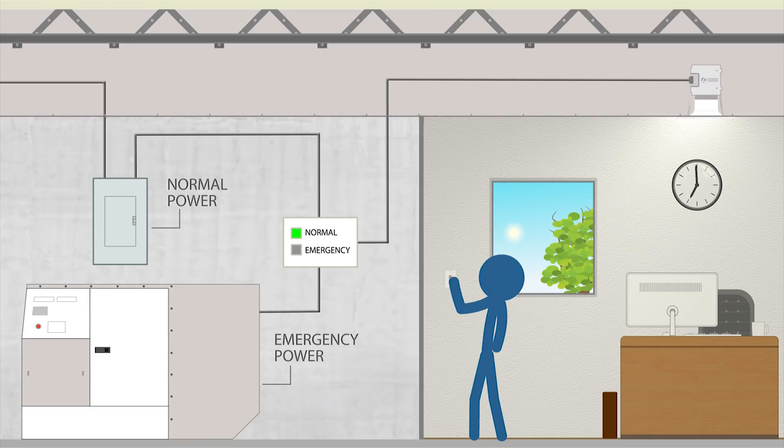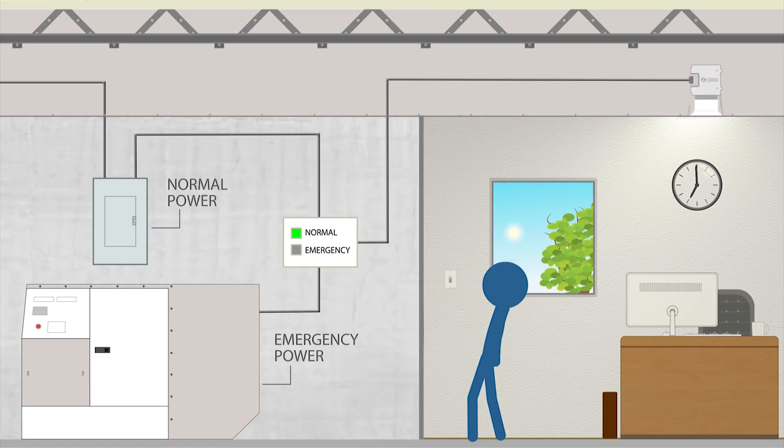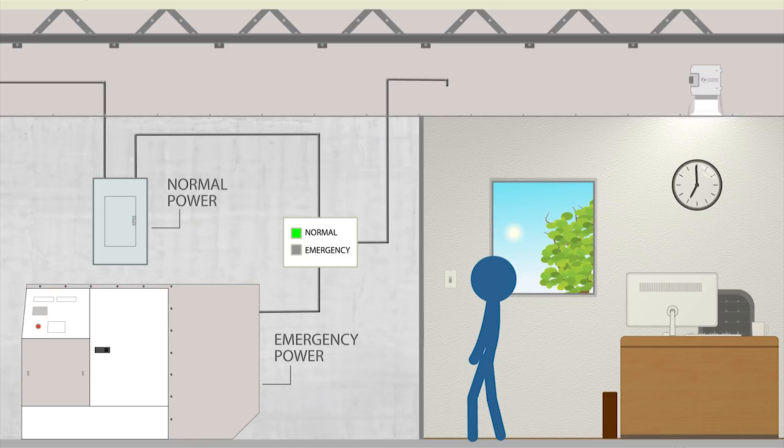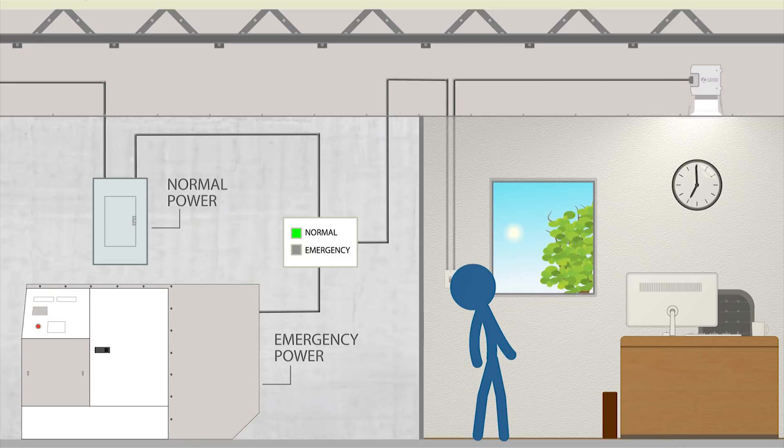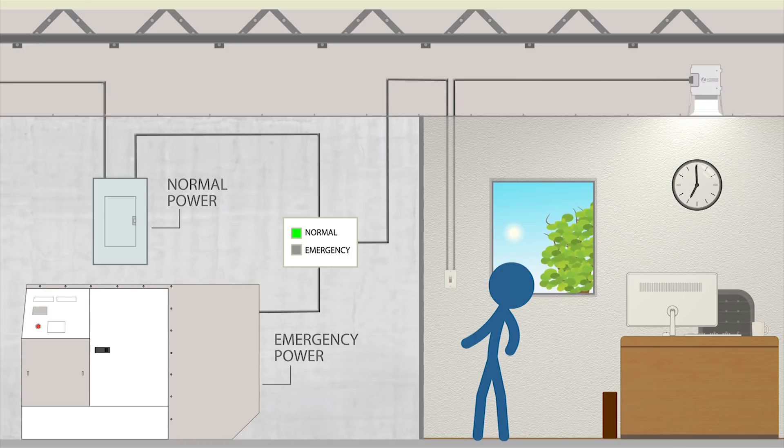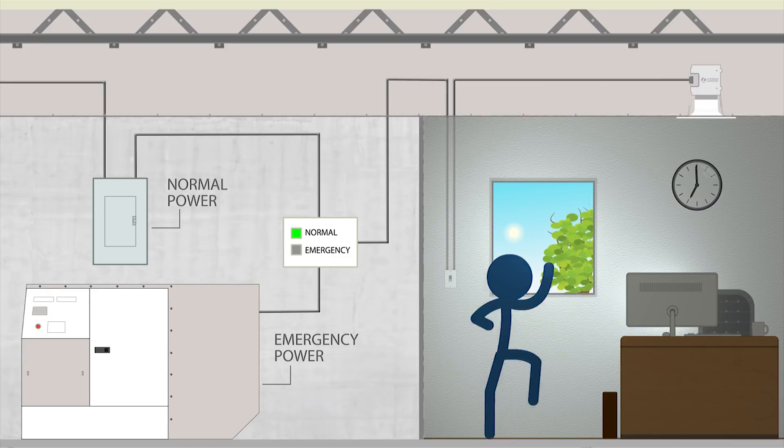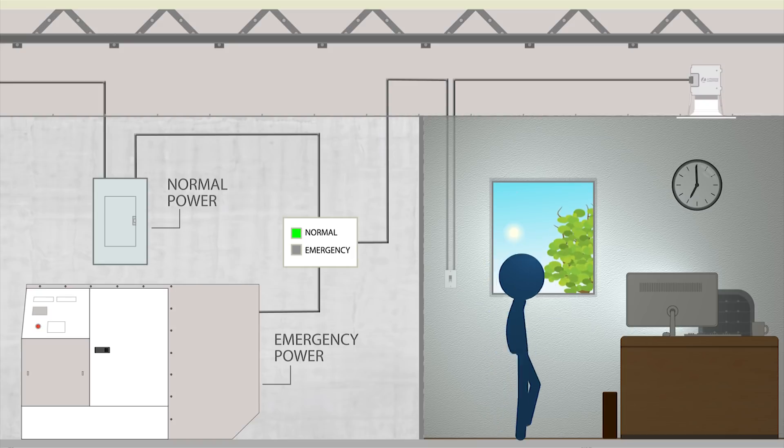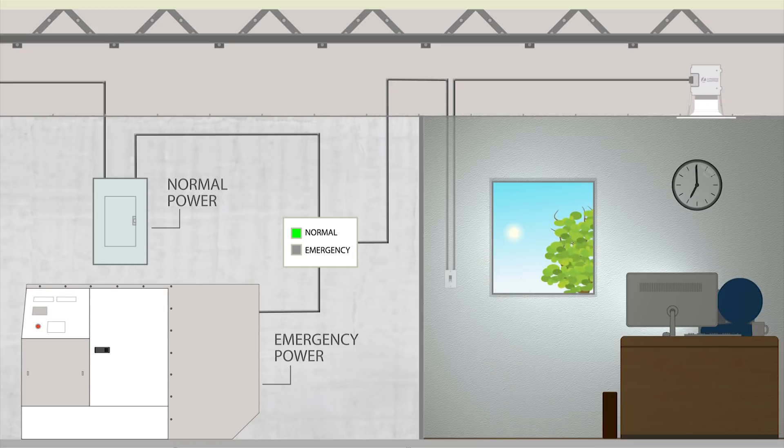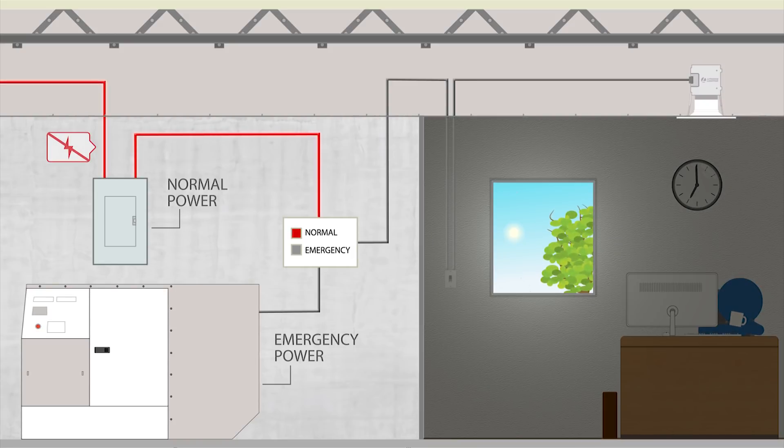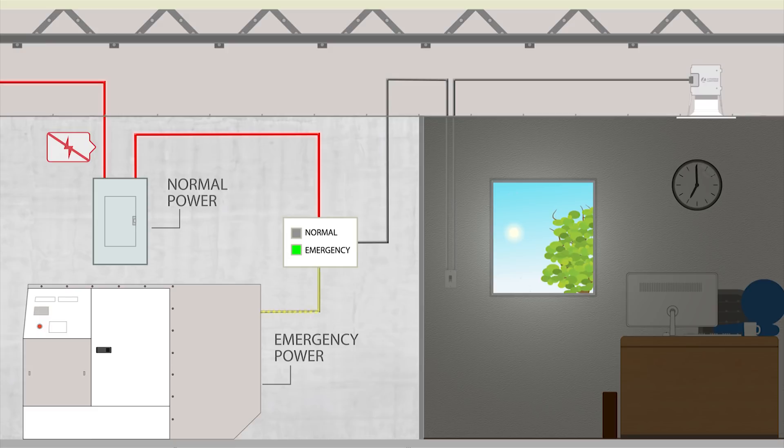To ensure that luminaires are operating properly during an emergency, a wall switch or other control device cannot be placed on the emergency circuit. The reason for this is to prevent these designated fixtures from being cut off from the auxiliary supply.